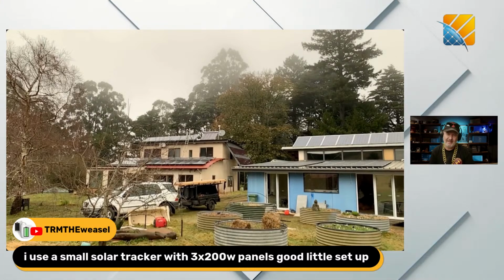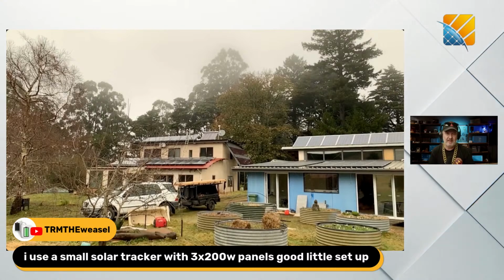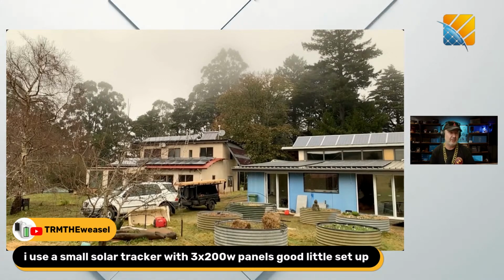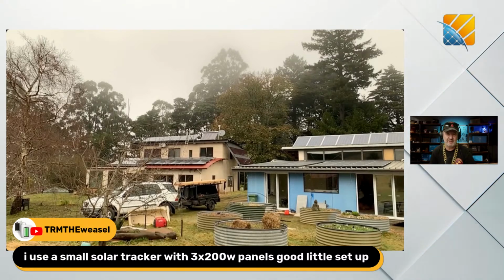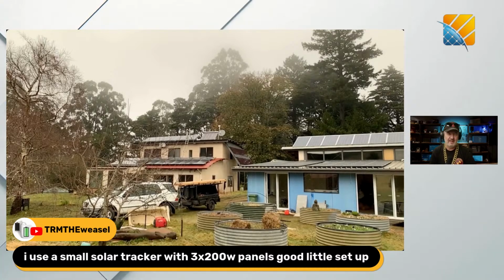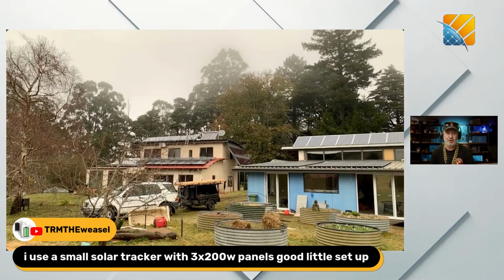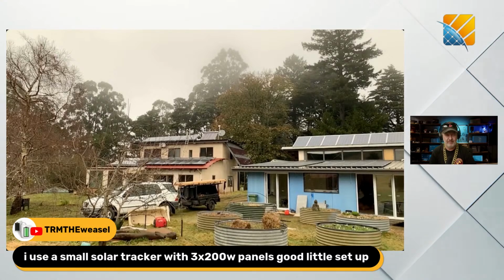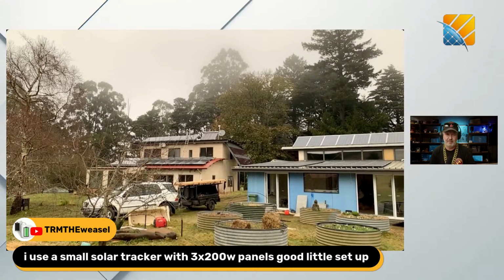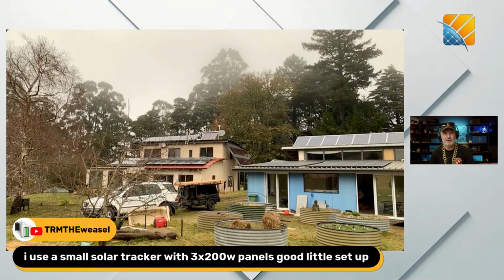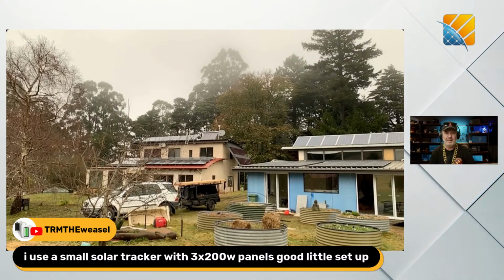But then tracking came back again, particularly for large-scale solar. What you're doing is getting more production per hectare off your solar farm, and also a much flatter generation profile. Single-axis tracking is now used in 70% of all new-build solar farms in Australia. I've got a couple of 30-kilowatt single-axis trackers out in the paddock as demonstration units, and what I've noticed, particularly in summertime, is they just turn on at full power around 8 o'clock in the morning - full power, 30 kilowatts, pretty much flat the whole day, till sunset. So you end up with something like a generator, basically - it just turns on because they're following the sun perpendicular the whole day long. That's a great generation profile, no peaky bit in the middle of the day.